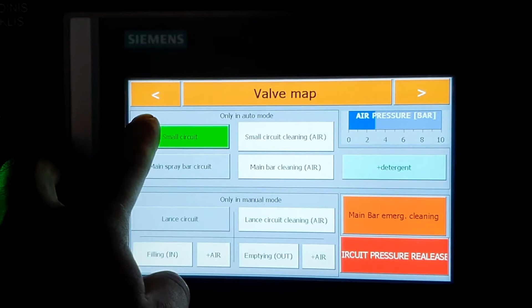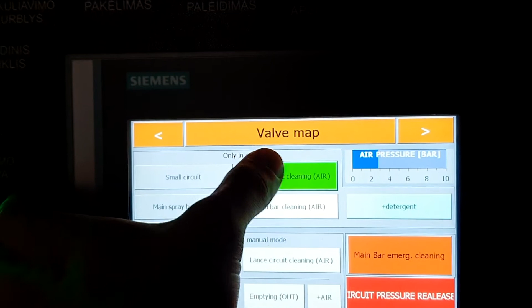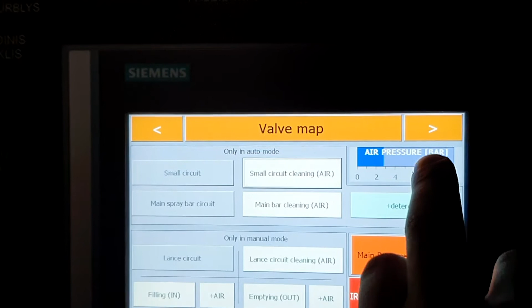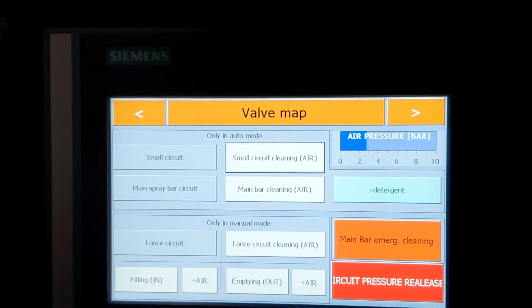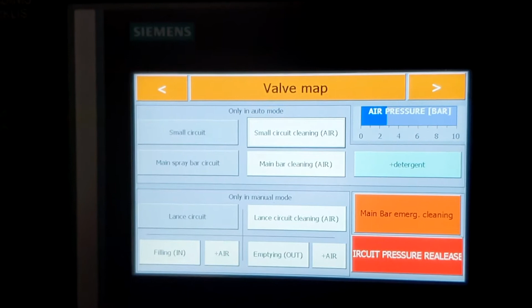After the small circuit has circulated, please remember to clean the small circuit with this button. We have to leave it for about 10 to 15 seconds, but always make sure that the pressure, which is located in the top right corner, is more than 7 bars. We clean the circuit once for 10-15 seconds. Then we wait until the pressure is correct again and put it back again, which turns the pressurized air through the circuit, so all of the different parts of the small circuit circulation are clean. After that, when the emulsion has the correct temperature, let's say 60 degrees Celsius, we are able to turn on the main spray bar circuit with this button.